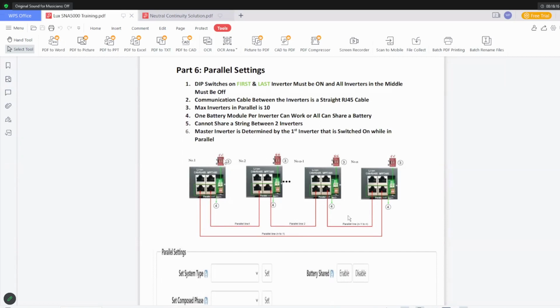As you can see, this is for the old model, but for the new model with blue dips, it's exactly the same. The first and last inverter must have their dips on, with the inverters in the middle having their dips down. For the communication cable, it's a straight RJ45 cable from the bottom left side of the first inverter connecting to the bottom right hand side of the last inverter. Then you daisy chain the insides of the other inverters together as indicated in the diagram, also using a straight RJ45 cable.